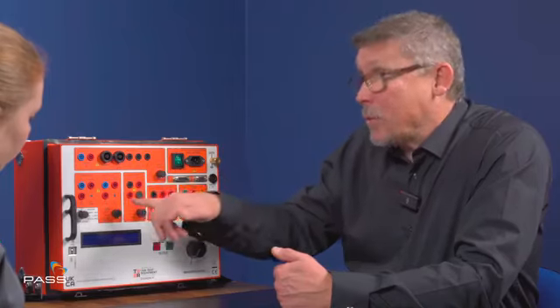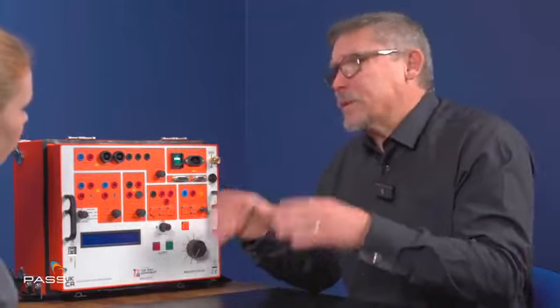And the next very important aspect is the timer. So they're the key critical points. There are other points, but they're the key critical points for this. So when it comes to the factory, the unit is fully calibrated, and we would anticipate that most companies should be looking to recalibrate or have these checked at least once a year, preferably by a company like yourselves at Pass or one of our other authorised distributors, or indeed with ourselves.